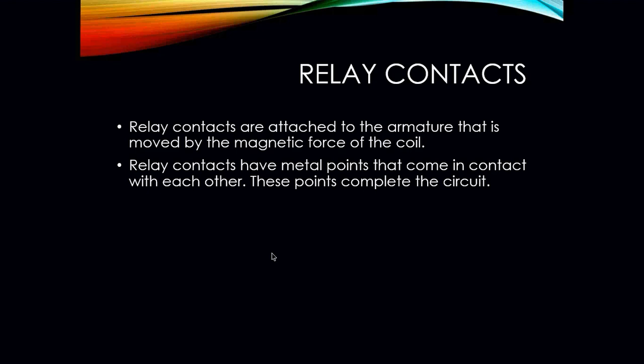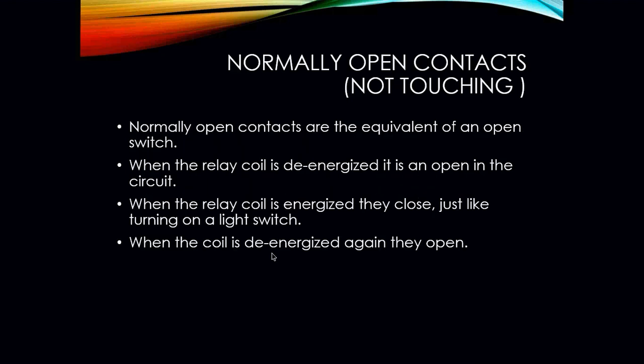The contacts on a relay are attached to an armature that is moved by the magnetic force of the coil. Relay contacts have metal points that come in contact with each other, and it's these two points that make the circuit. Normally open contacts are the equivalent of an open switch. When the relay coil is de-energized, those contacts are going to open the circuit. When the relay coil is energized, they close those contacts just like a light switch. And then when that coil is de-energized again, they're going to open.